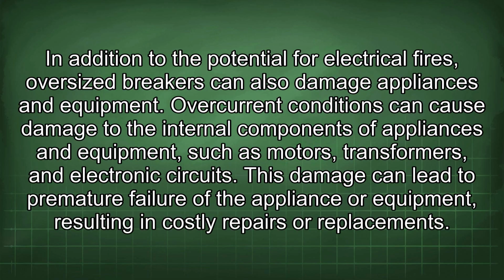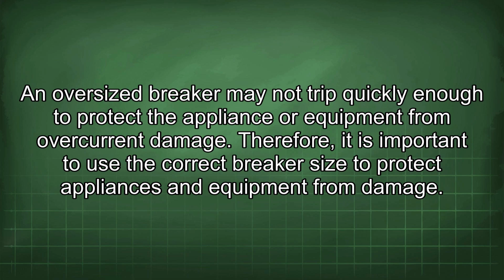In addition to the potential for electrical fires, oversized breakers can also damage appliances and equipment. Overcurrent conditions can cause damage to the internal components of appliances and equipment, such as motors, transformers, and electronic circuits. This damage can lead to premature failure of the appliance or equipment, resulting in costly repairs or replacements. An oversized breaker may not trip quickly enough to protect the appliance or equipment from overcurrent damage. Therefore, it is important to use the correct breaker size to protect appliances and equipment from damage.